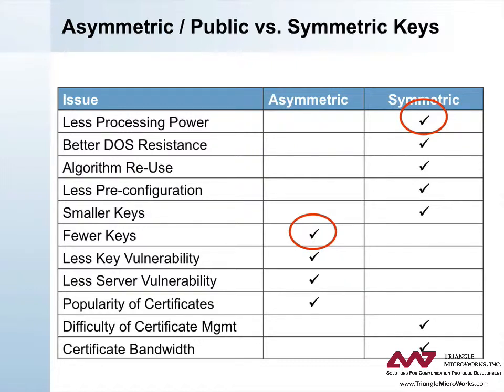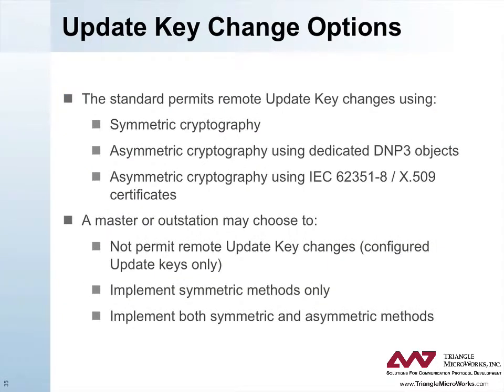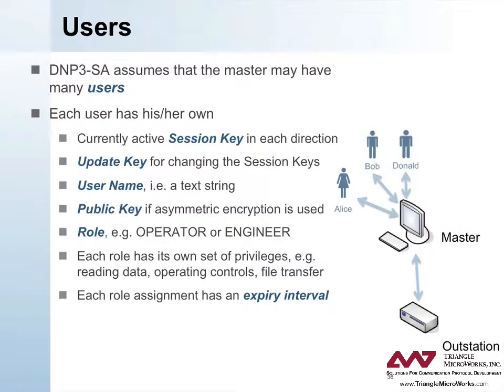A white paper is available from the DNP3 technical committee discussing this comparison in more detail. The DNP3 specification permits remote key update changes using symmetric cryptography, asymmetric cryptography using dedicated DNP3 objects, and asymmetric cryptography using IEC 62351-8 or X.509 certificates. A master or outstation may choose to use configured update keys only and not permit remote update key changes. It may also implement only symmetric methods, or it may implement both symmetric and asymmetric methods.